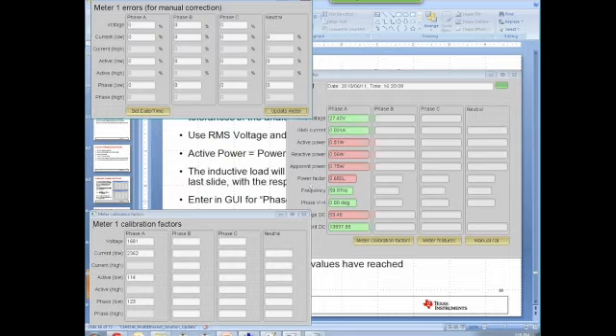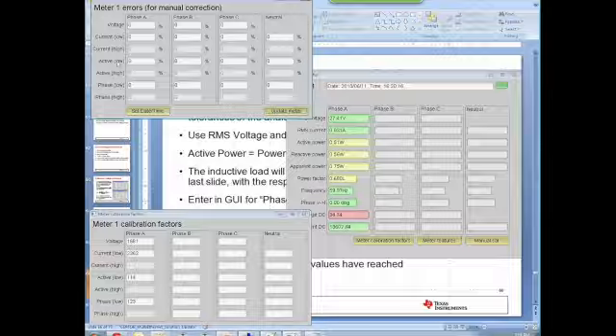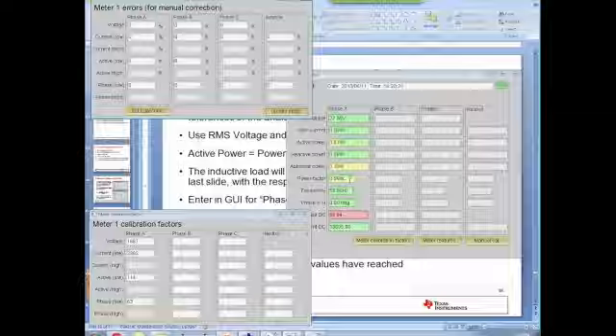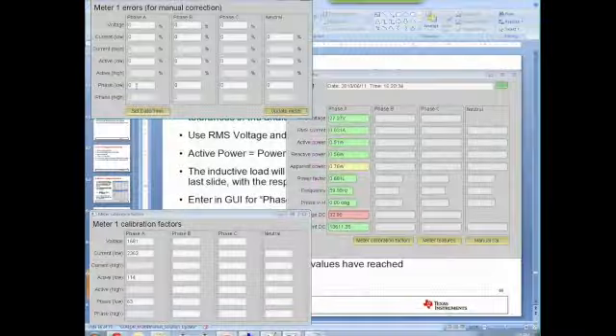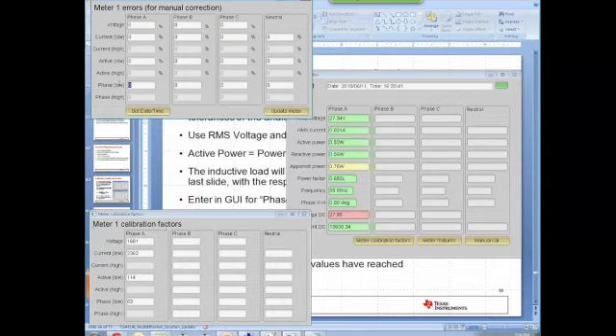You have to let these stabilize again. You can see that the power factor went up. We're up at 0.68 now, and we want to be at 0.72. So we'll try to go down even lower. Let's do another minus 60 on mine. So we're down to 63. We'll let this stabilize. What was that? This phase low, you enter a positive or negative value to add or subtract from this phase calibration data. Yeah.